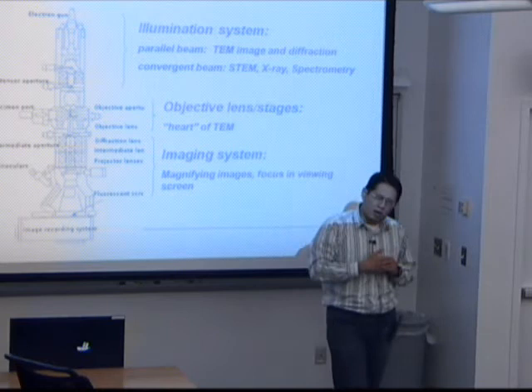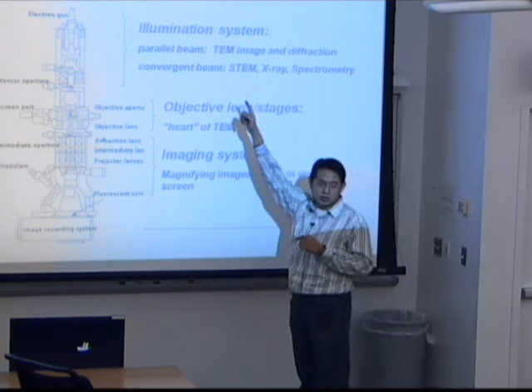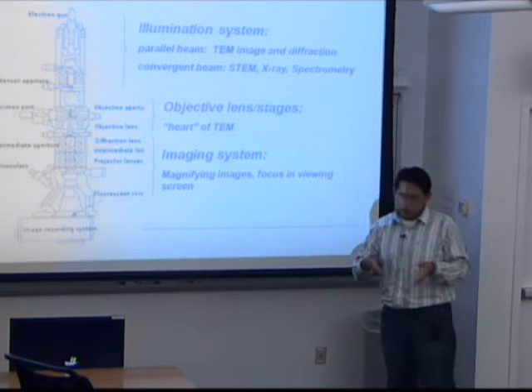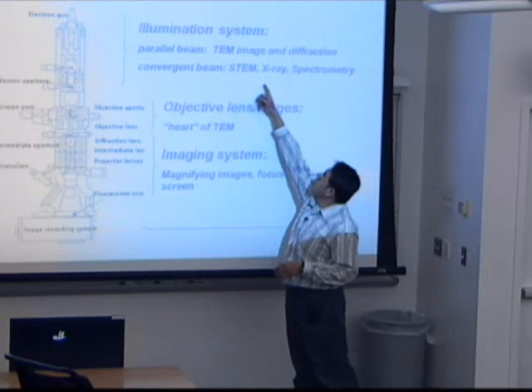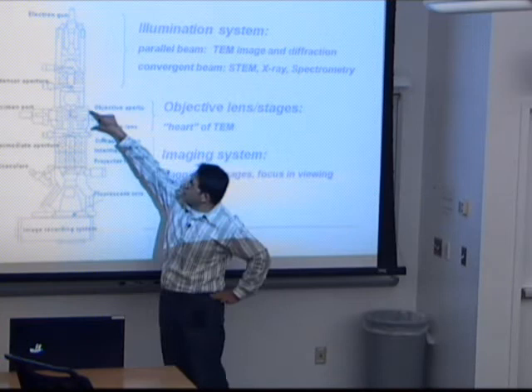In the two main functions of TEM, we use a parallel beam to get TEM images or get the diffraction pattern. You can also use a convergent beam to analyze or measure the composition of the sample, or measure the chemical property of the sample. This is often called STEM, X-ray spectroscopy.